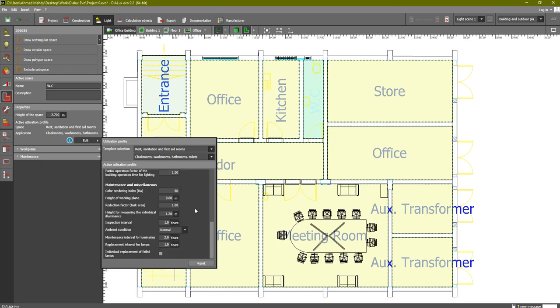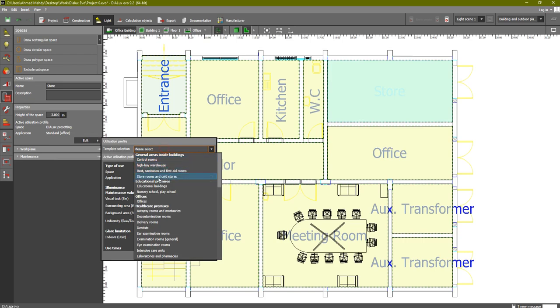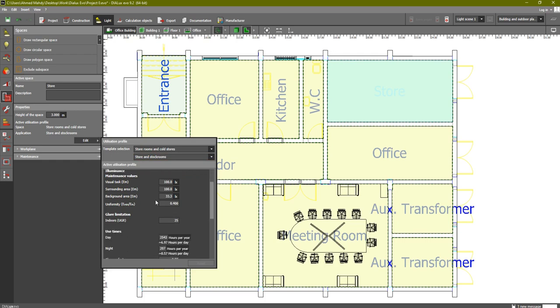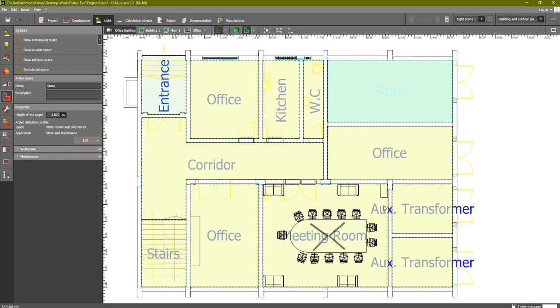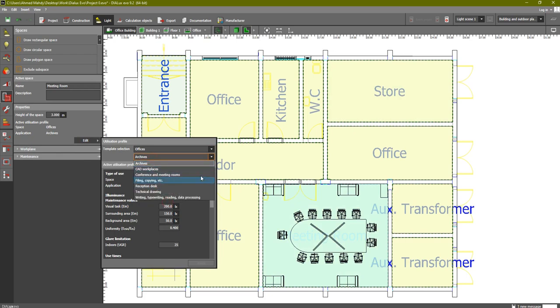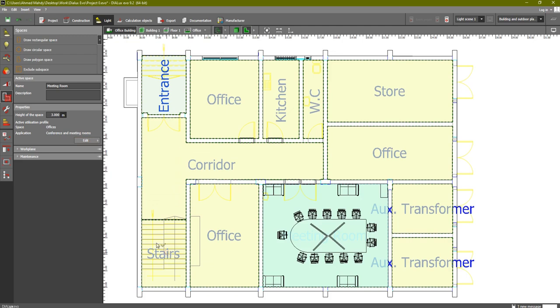For the Store, click Edit and go to Store Rooms and Cold Stores, where you find Store and Stock Rooms. The normal lux value is 100 lux and the uniformity is low at 0.4. For the Meeting Room, it falls under Office — Conference and Meeting Room — and requires 500 lux with a uniformity of 0.6.